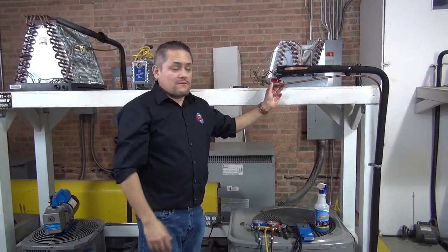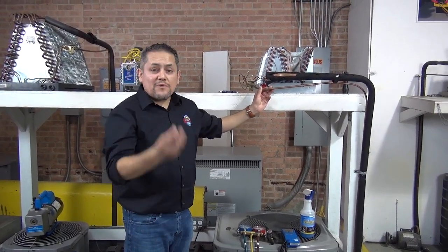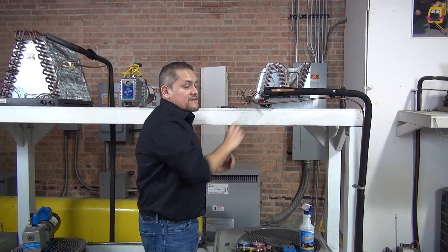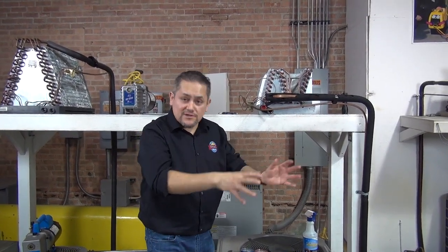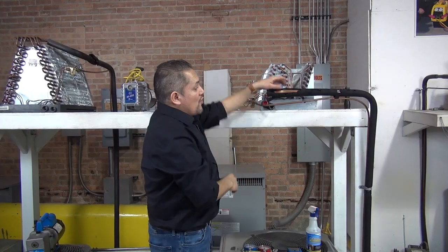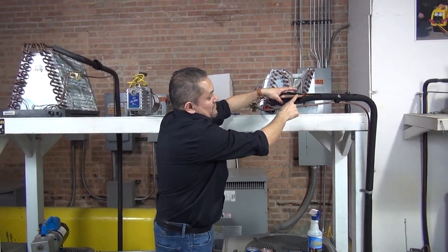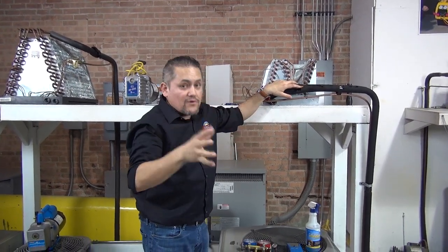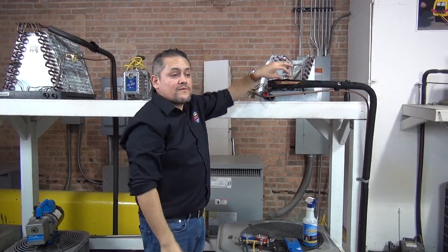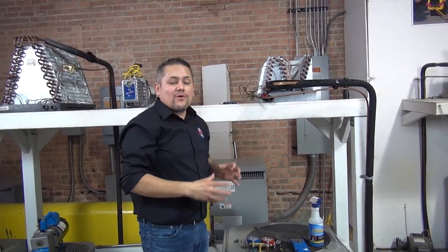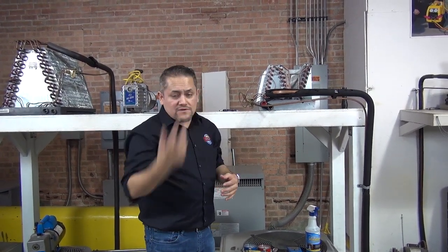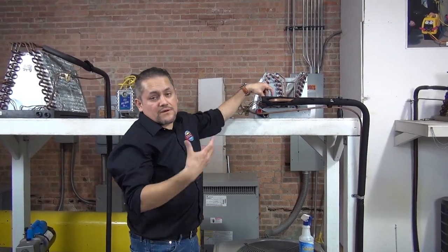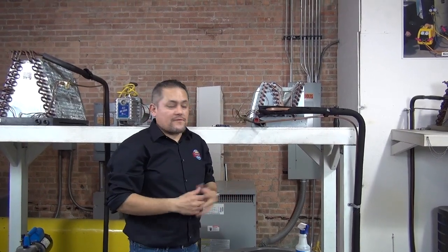Sometimes, on different service calls, there will be oil spots. Sometimes you will find oil spots around the condenser outside. Sometimes the oil will be between the copper pipe and the insulation right here. You're going to see a lot of oil. Once you see that oil right there, then you know that it's leaking from the suction line. So that's another one. Anywhere you see oil, there's probably a leak in the system. If you guys remember, there are only two things running through the whole system: refrigerant and oil. Once you have a leak somewhere, the oil will start to come out.